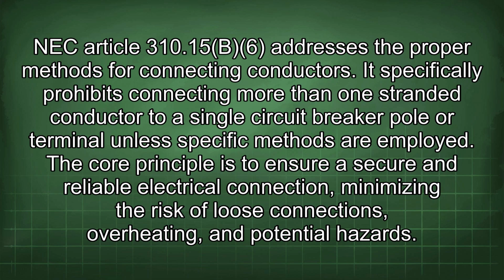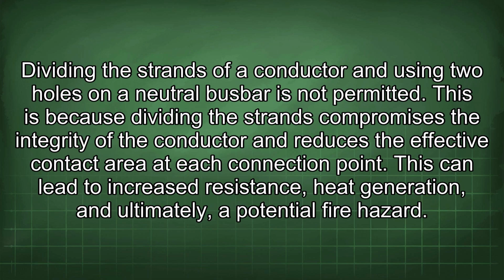overheating, and potential hazards. Dividing the strands of a conductor and using two holes on a neutral busbar is not permitted. This is because dividing the strands compromises the integrity of the conductor and reduces the effective contact area at each connection point. This can lead to increased resistance, heat generation, and ultimately, a potential fire hazard.